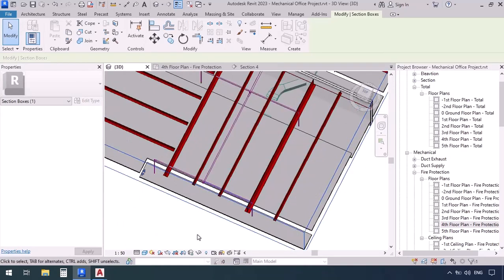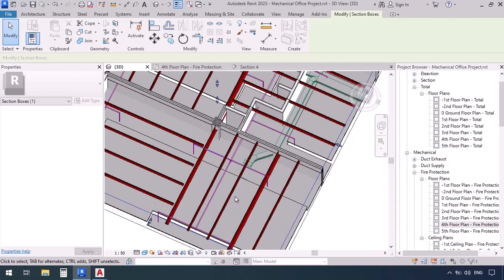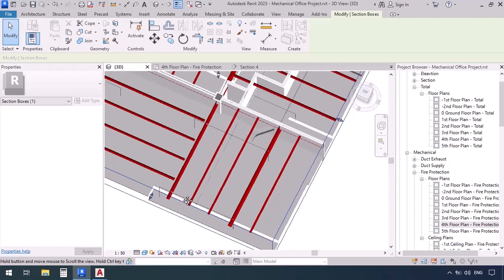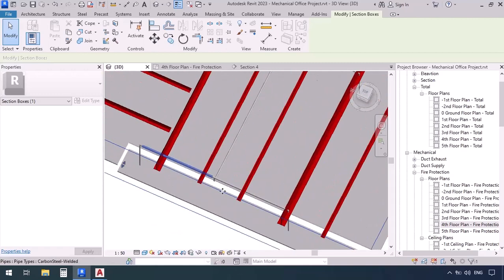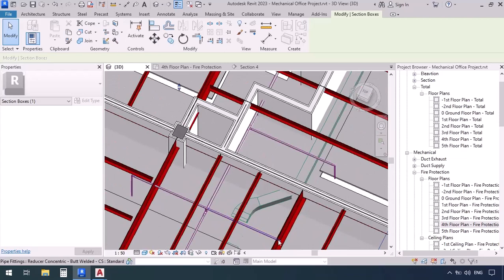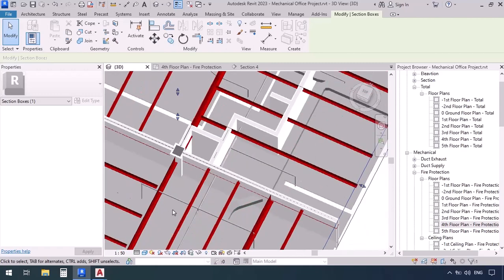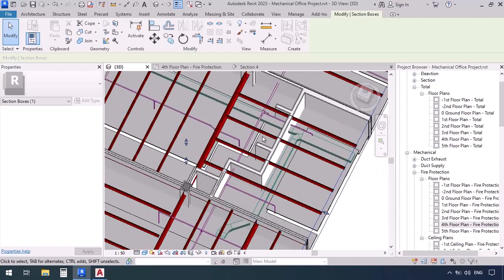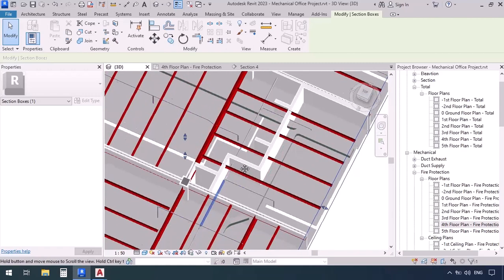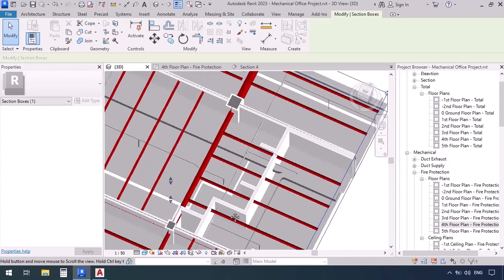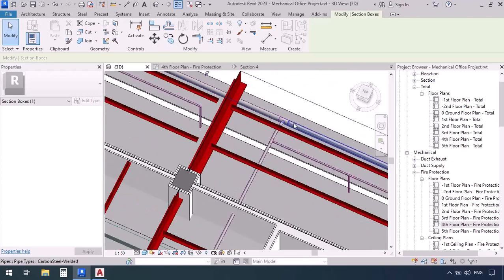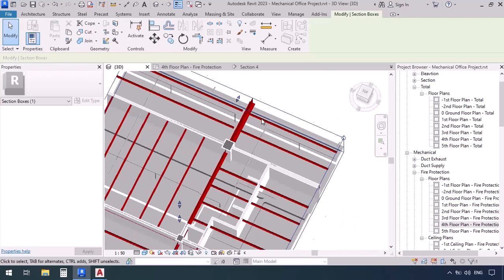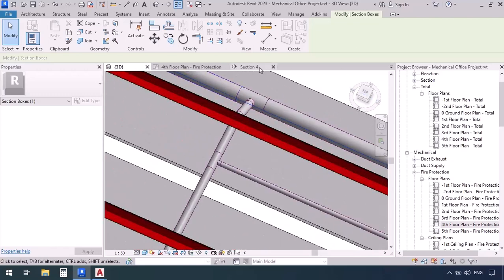Now these pipes are going through the beams so we're gonna have to check to see if there's anything we can do to fix this crossing. So now we have this one and another one and 3 and 4. Now if I try to make 4 splits it might make things a little complicated. So instead I can just change the elevation from this part on out. Basically I will be lowering the elevation of this entire line, or I could just undo this split here like I would be drawing this entire part with lower elevations.